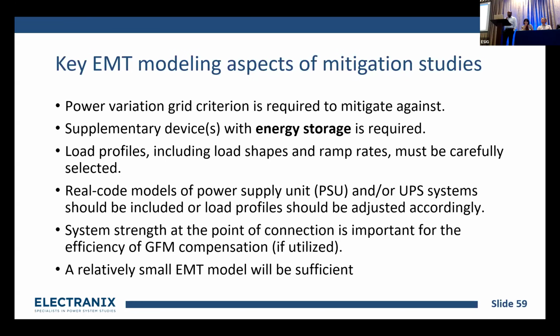The real code models of these units. In other terms, if you look at a data center, we have a bunch of different categories. We have cooling loads and all sorts of these. And then on top of that, a major part is the IT load, which could be 70%, 60%, whatever that number is. That is the main part that we are trying to mitigate, because that is the load which is fluctuating drastically. So to simulate that in a correct way, we need the power supply models or the UPS models. In other terms, we need the real code models.